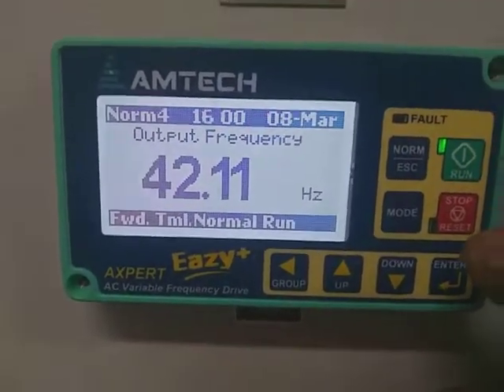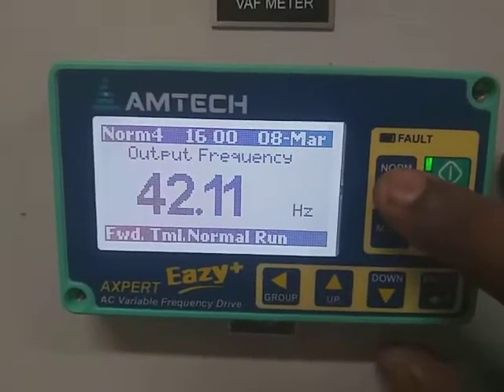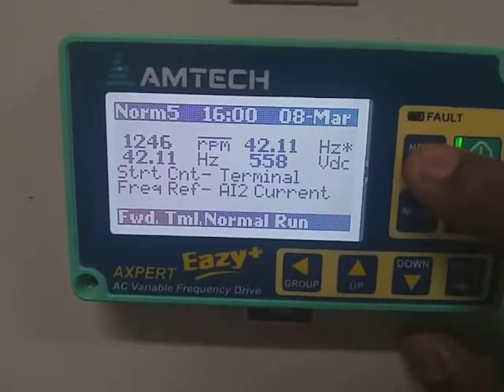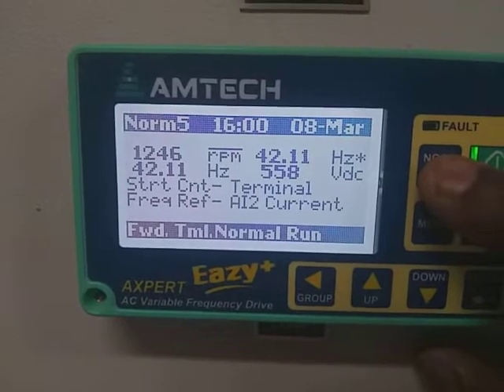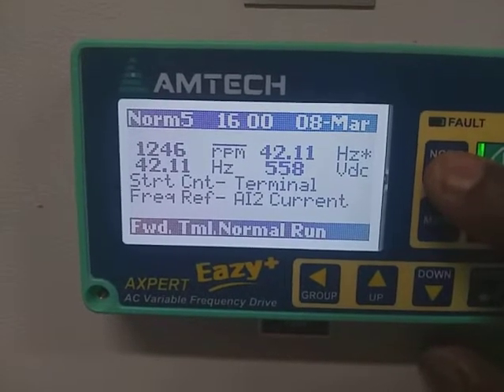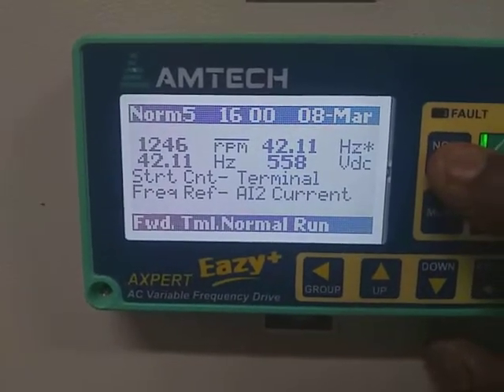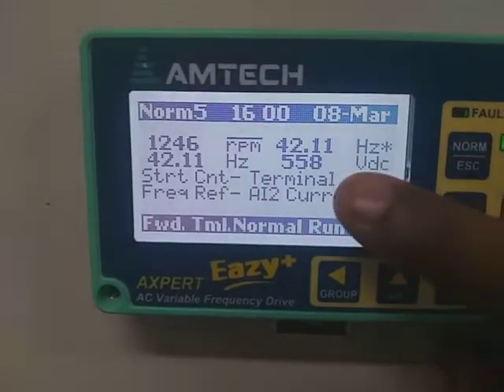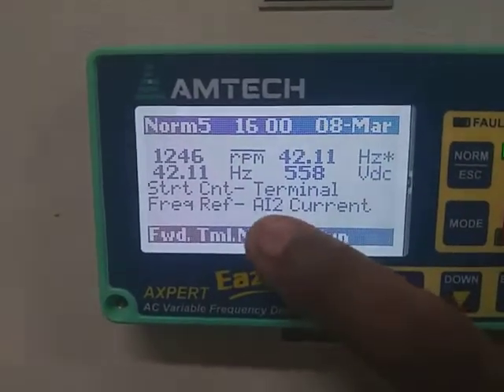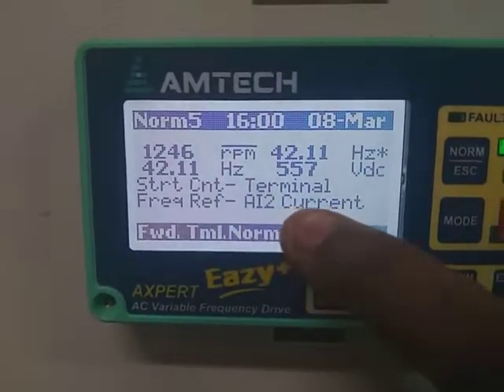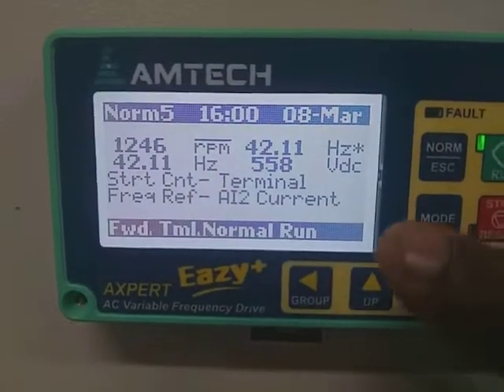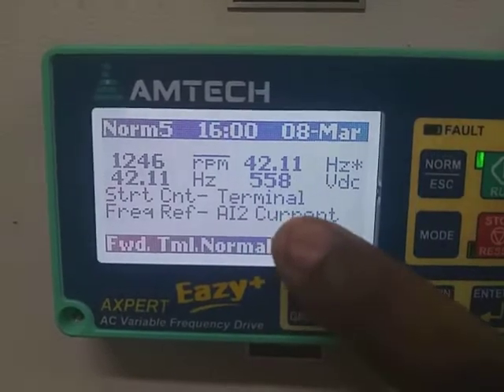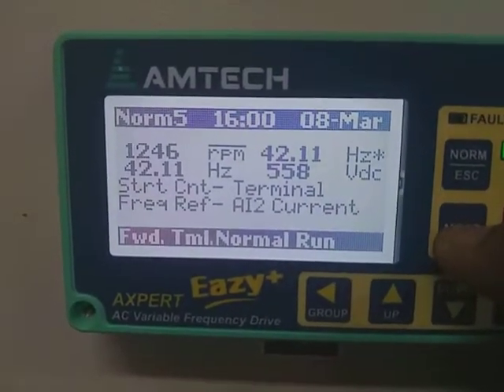You only have to press the escape button and every parameter will show. Start control means where the control is from — terminal or remote, it will show terminal or remote. If it is in local mode, it will show local. Frequency reference will show AI2 current — meaning from DCS, 4-20mA is coming. If LCL is selected, it will operate from HMI.